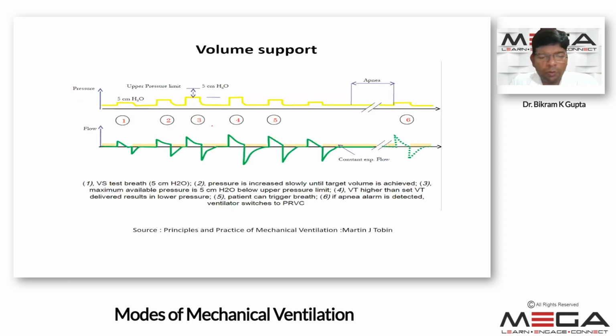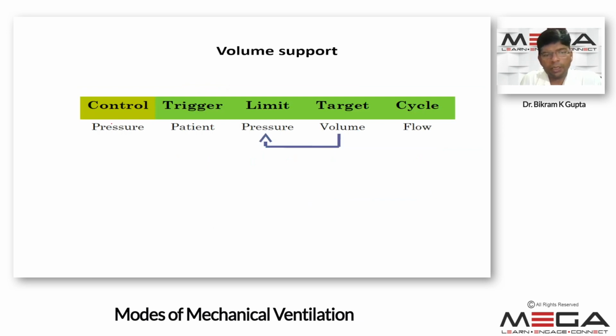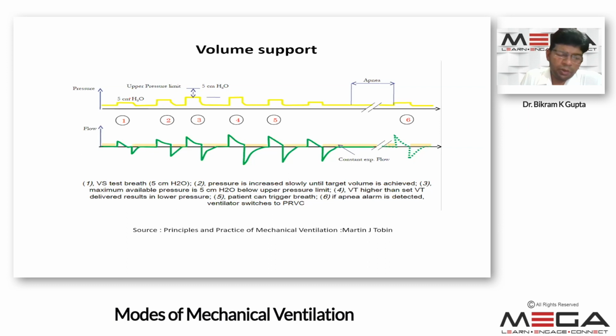Now coming to the breath-to-breath dual mode of ventilation. In this, the example is volume support, and here the control is the pressure, triggered by the patient, the limit is the pressure, the target is the volume, and the cycling is flow cycling. When we put the patient on it, we start with 5 centimeters of H2O of pressure, and with this pressure the test breath measures how much tidal volume the ventilator achieves. Then gradually the pressure limit will increase, up to a maximum of 5 centimeters below the upper pressure limit. After achieving the target volume, if the patient is able to achieve that tidal volume, then gradually the pressure support decreases. If the patient triggers a breath, the ventilator provides a volume support breath. If the patient is not able to trigger and there is an apnea alarm, then this volume support mode will switch to the PRVC mode. I will discuss this in a later slide.